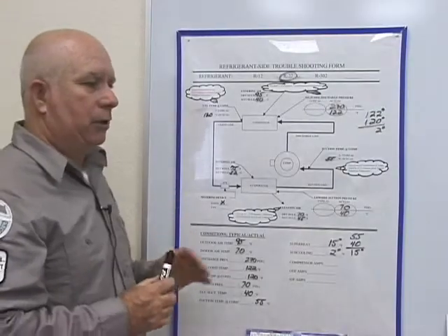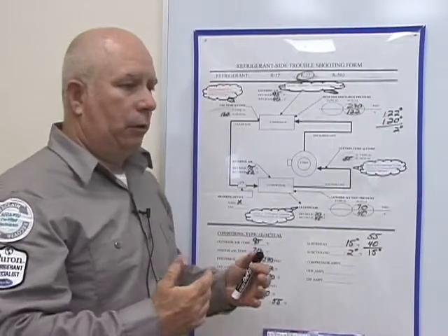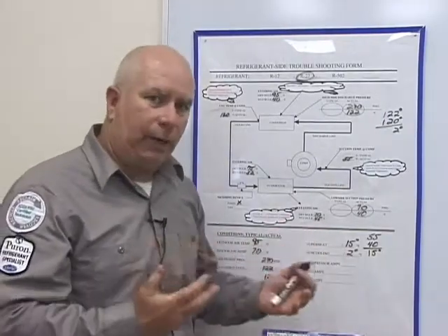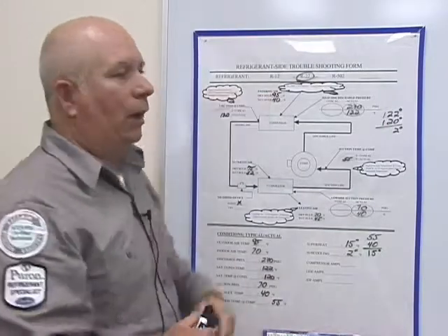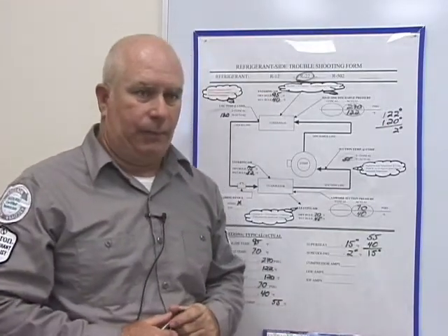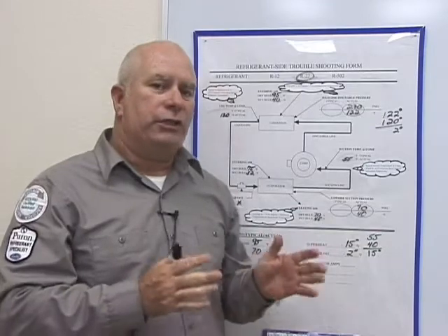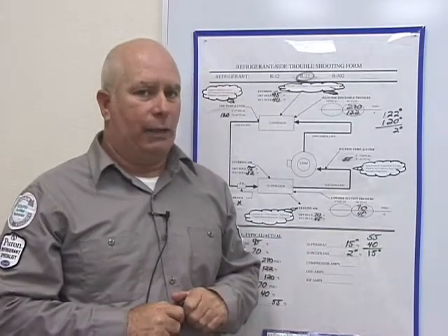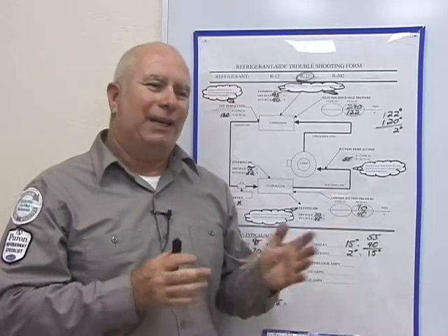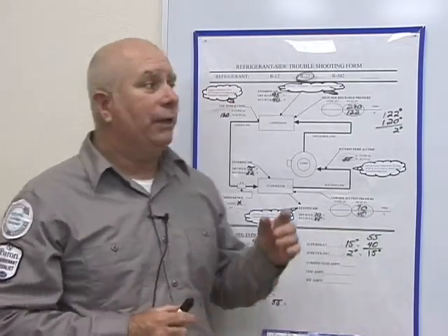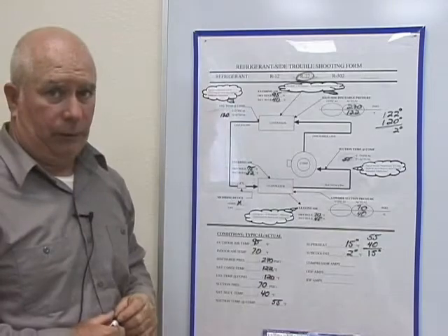Now it becomes important to know, what do I compare this with? Well, that's all fine and dandy if I go out on a 95-degree day. But remember, your season startups normally do not happen in mid-July. They normally happen in the April, May timeframe when it isn't 95 degrees.